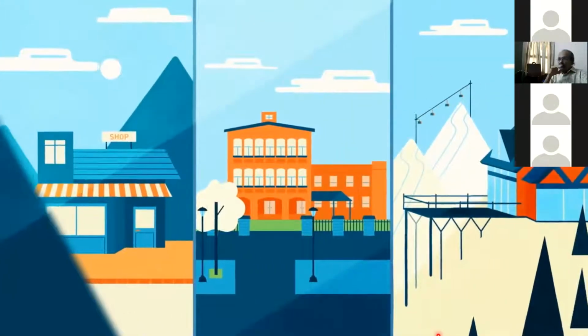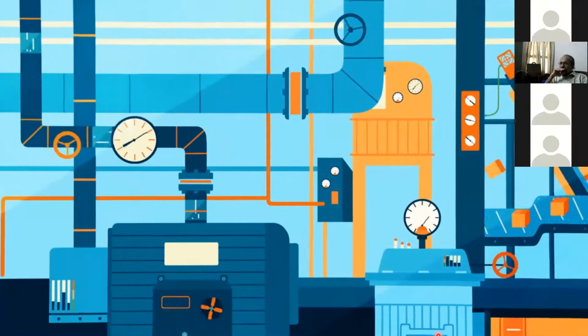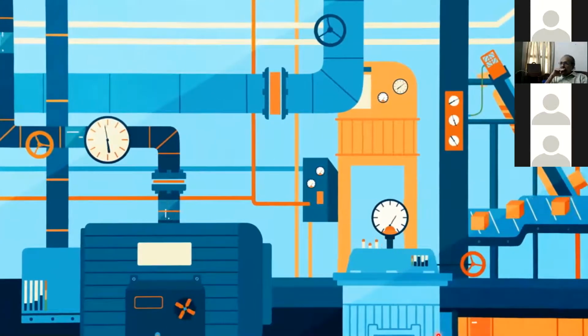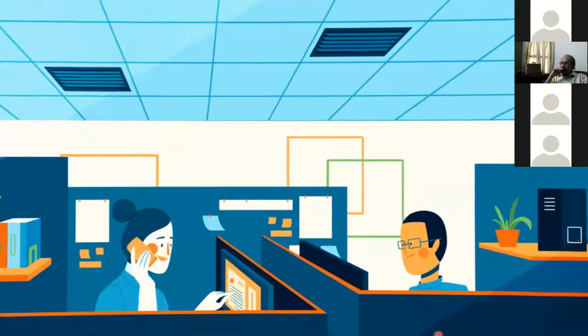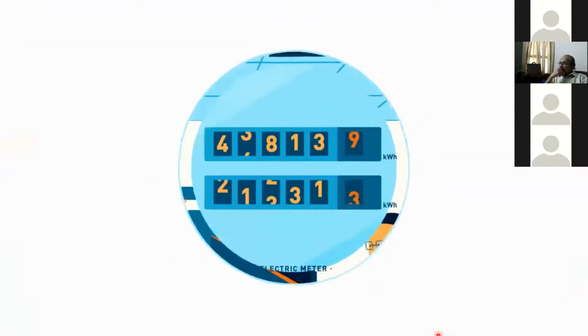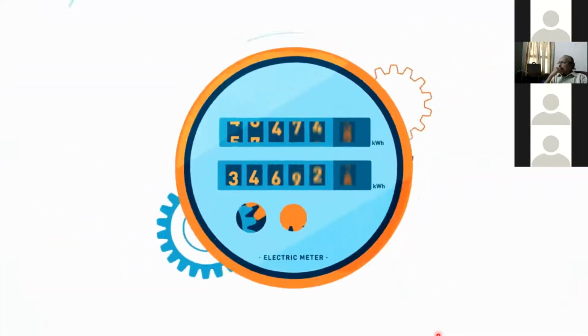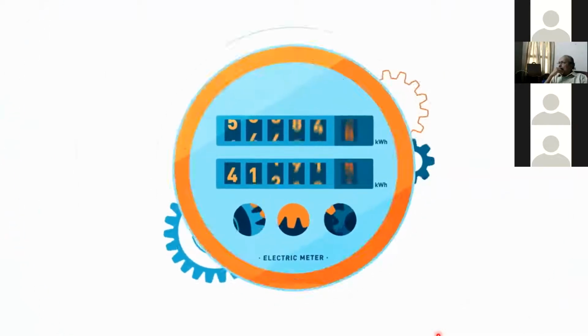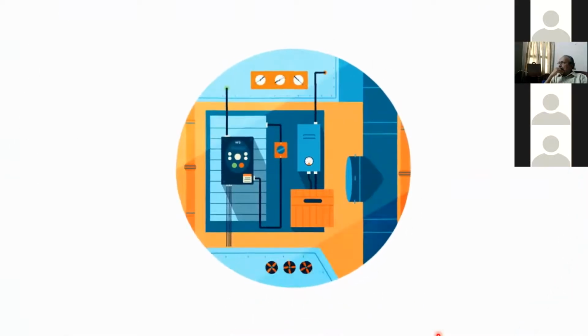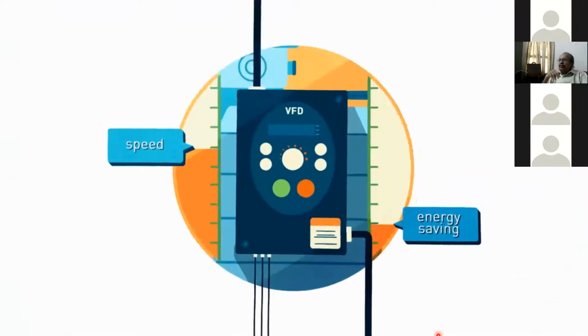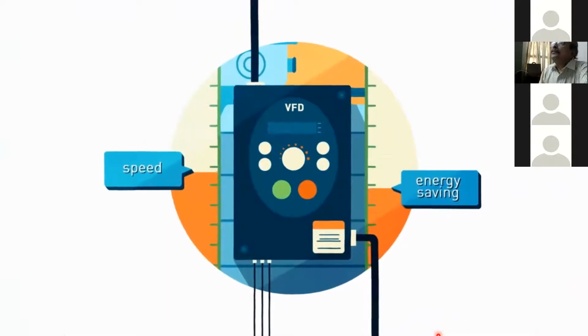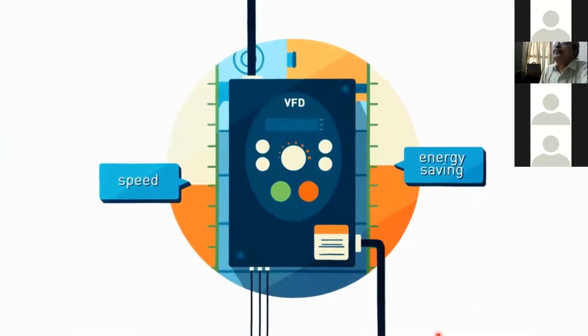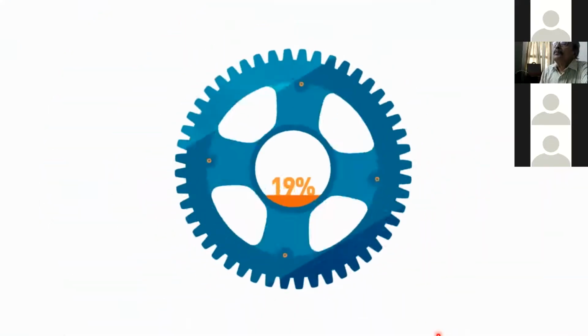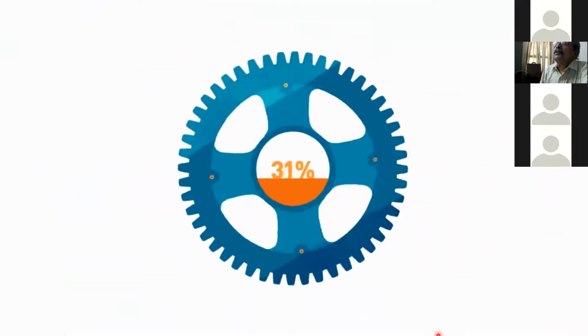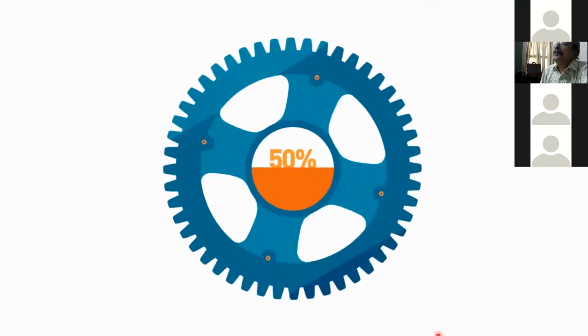If you're in business, you're paying to power motors, whether to supply ventilation, run pumps or industrial equipment, or even just to heat and cool your space. Many motors run at a constant speed, and they don't have to. This wastes energy and wears out your equipment faster. A variable frequency drive, or VFD, slows down a motor, decreasing overall energy usage and reducing wear and tear on the motor without sacrifice to comfort or performance. A simple 25% decrease in motor speed can save up to 50% in energy costs.